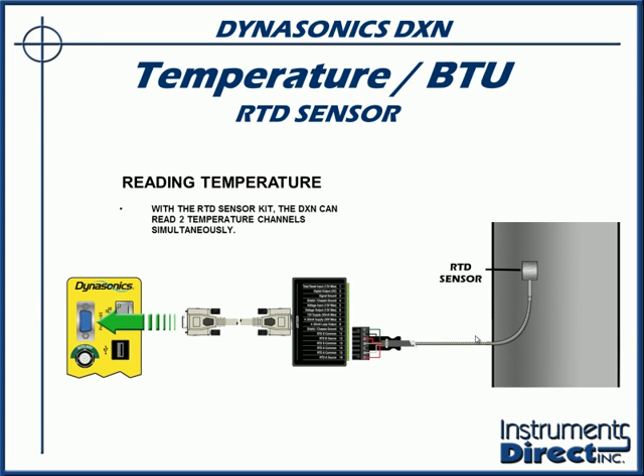Should you want the optional temperature energy management kit, you plug that in to your I/O output, and basically with the optional temperature kit, you get a couple of strap-on RTDs. In this case, you would monitor flow on the supply, temperature 1 on the supply, temperature 2 on the return, and collect all that data, and the device will actually give you an energy or BTU output. So that's a very popular application now.